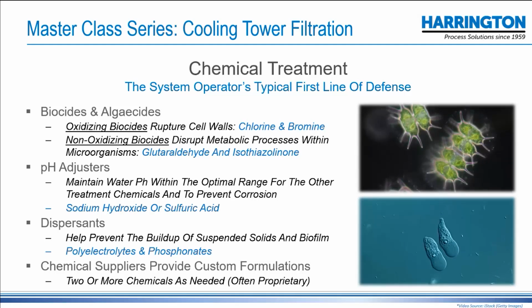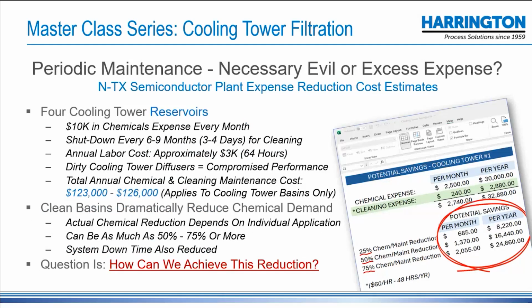They're very expensive. I was actually at a semiconductor outfit up in North Texas that I asked if they had cooling towers. Yes. I asked, how much are you spending on chemicals? And he did the calculation. He said, well, the totes are $20,000 a piece, and we go through one every 2 months. So that's $10,000 of chemical expense every single month. And they shut down about every 6 to 9 months for 3 or 4 days of cleaning. So labor cost about $3,000. And the total annual spend of labor and chemicals was over $125,000.